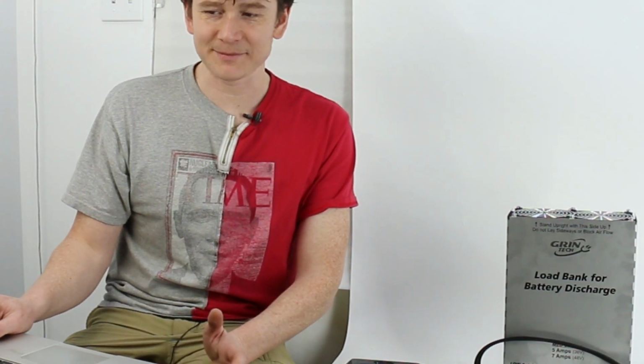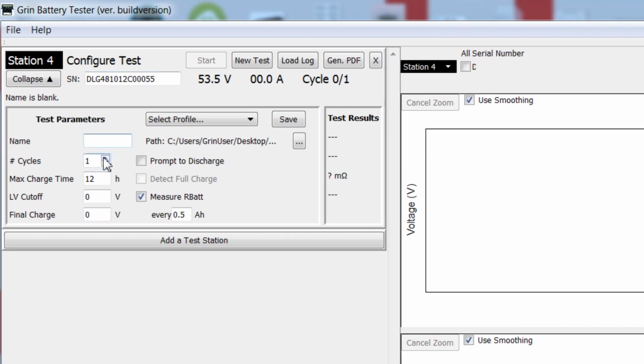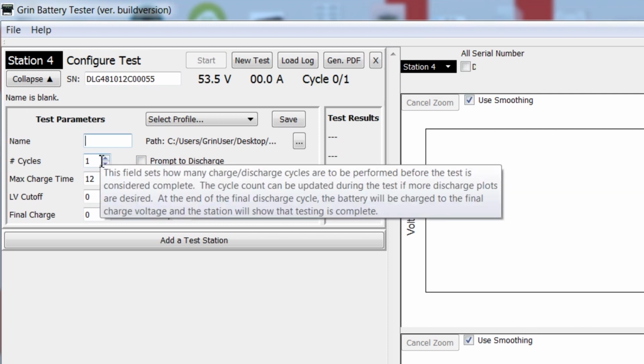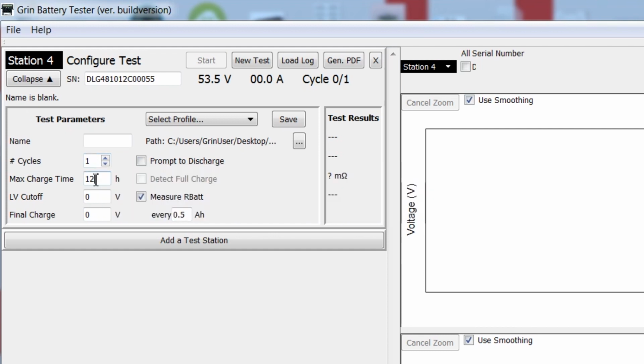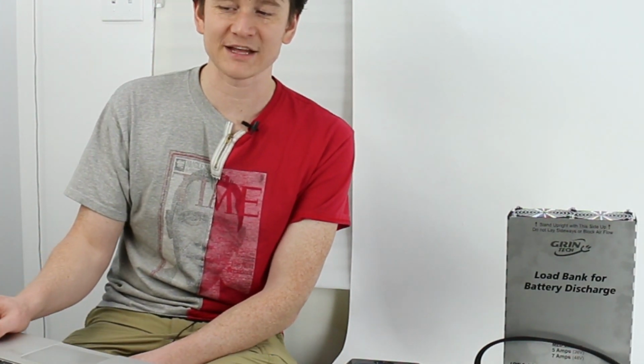Now here's where we set up the test parameters we want. We can choose how many times we charge and discharge the battery pack, that's the number of cycles. We're going to do just a simple discharge test for this one, discharging the battery once and then partly charging it afterwards to end the test. The maximum charge time, if doing multiple cycles, is the duration it will continue allowing the battery to charge before switching to discharge, so you need to make sure that's long enough for a full charge after it's been fully depleted.